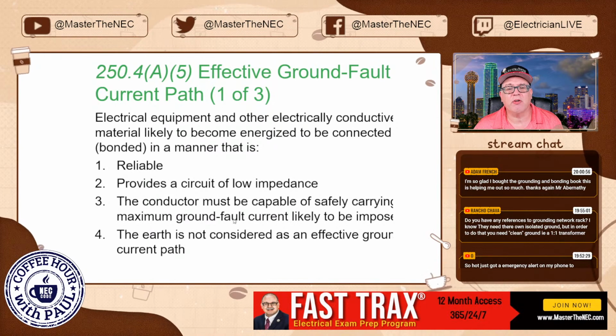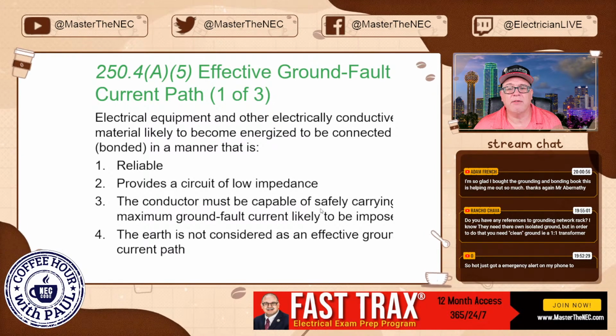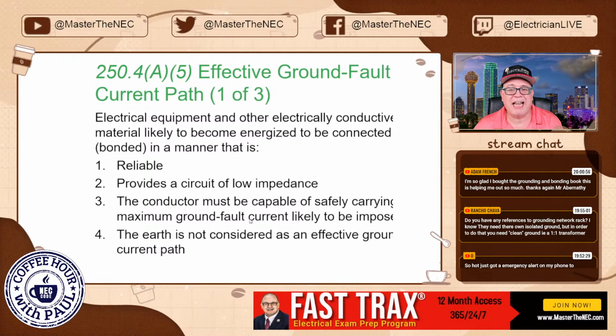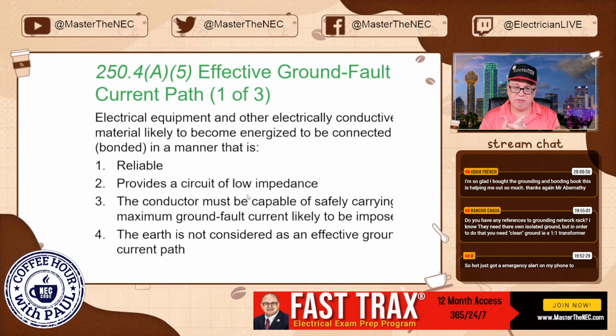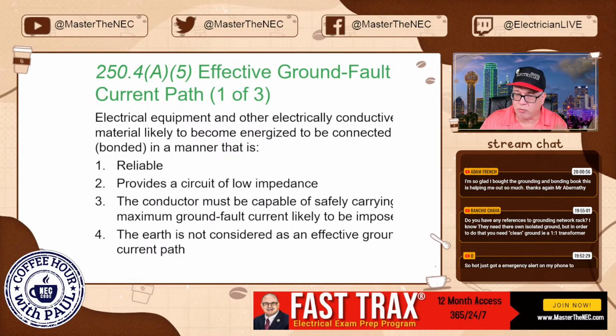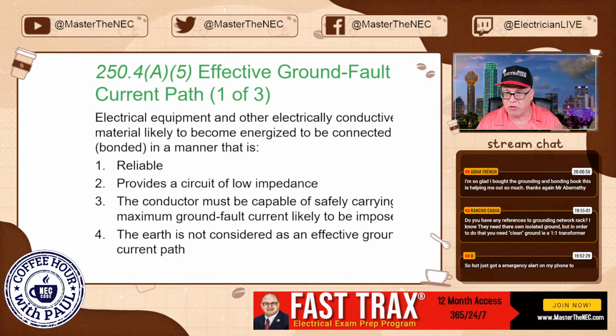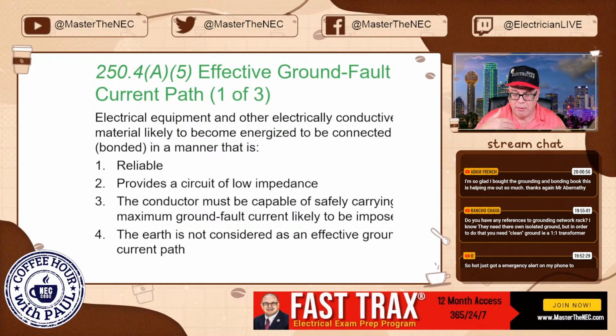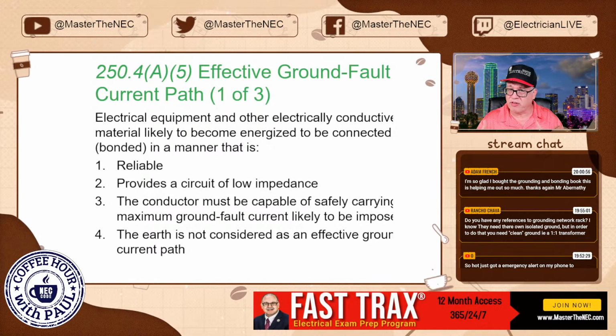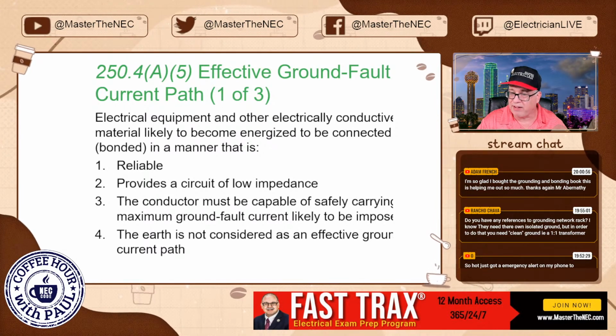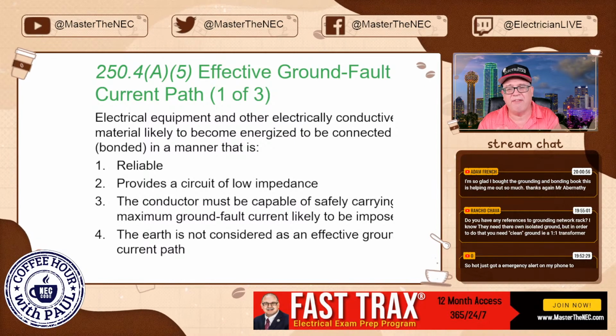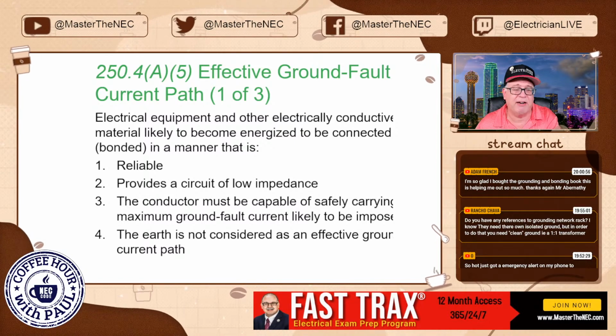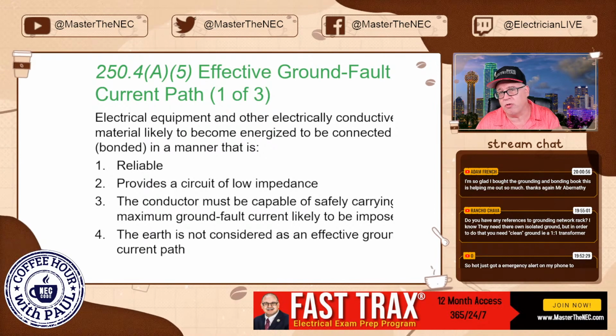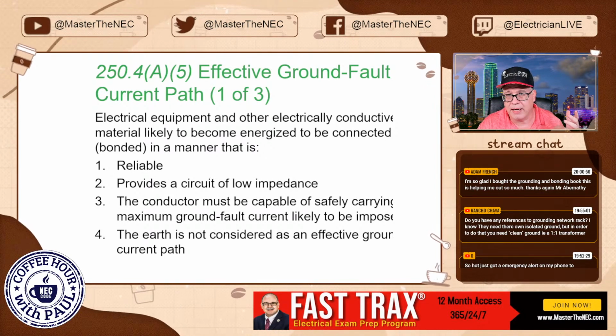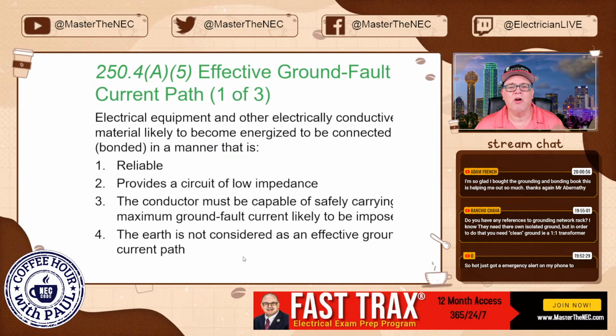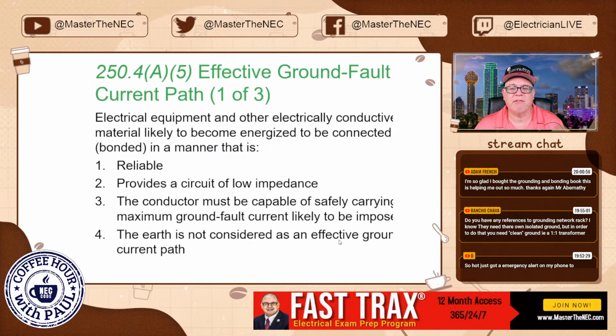Number 3, the conductor must be capable of safely carrying the maximum ground fault current likely to be imposed on it. And I can tell you right now, if we're doing things like equipment grounded conductors, we're basing those on the size of the overcurrent device. We're going to go to 250.122. And if we do parallel runs, we're going to be full-sized equipment ground based on the overcurrent device in all raceways. We're going to have a conductor that is capable of safely carrying the maximum ground fault current imposed on it. Clear that breaker, okay? The earth is not considered an effective ground fault current path.